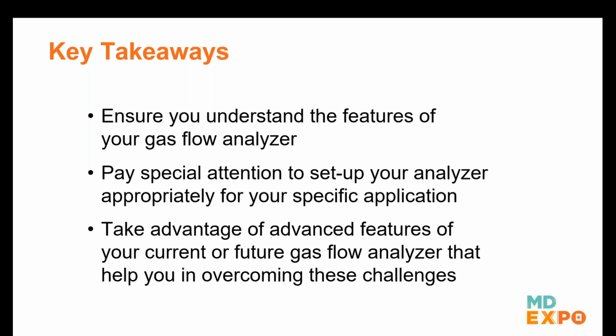And last of all, take advantage of the features that we're talking about here. A lot of people don't take the time to learn their device. They go to class and they say, okay, your volume number has to match this volume number, your pressure number has to match that one, your PEEP matches, the O2 percentages, those have to match. You do multiple settings on the device under test and you take multiple readings and you're done. But if you take a little bit of time and look at these advanced features, they'll help teach you what you're actually measuring, okay? I know it takes a lot of time and you're very busy, but in the long run, it will save a lot of headache. It will increase your accuracy. It will increase your efficiency.